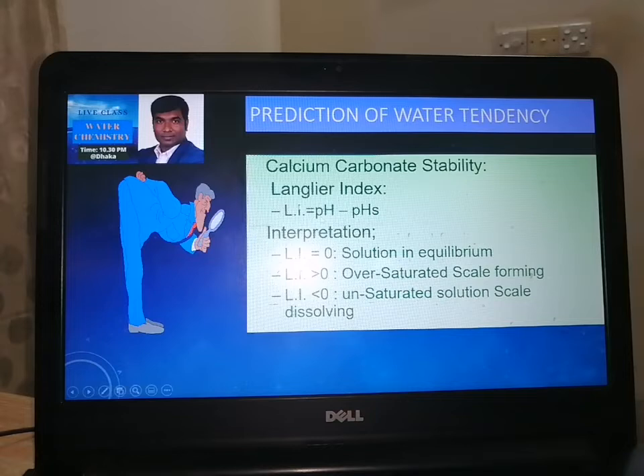Just remember, when we calculate LSI, if the LSI number comes equal to 0, that's a very ideal situation which normally never happens. But if it is greater than 0, that means scaling can form. And if it is less than 0, that means corrosion can happen.